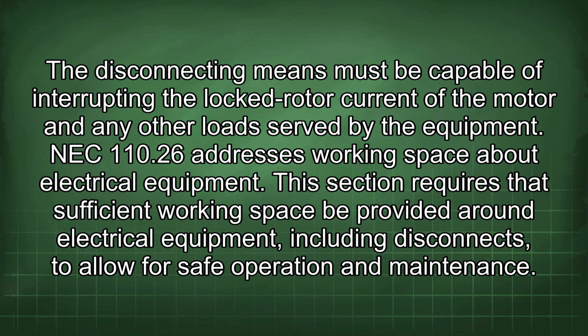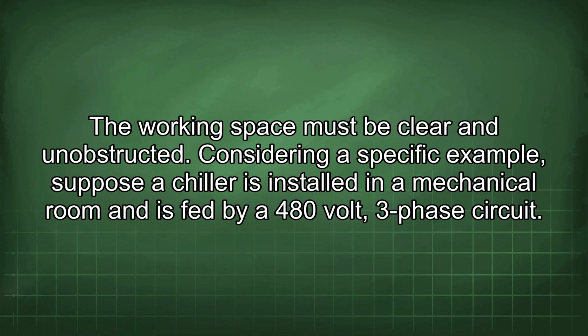NEC 110.26 addresses working space about electrical equipment. This section requires that sufficient working space be provided around electrical equipment, including disconnects, to allow for safe operation and maintenance. The working space must be clear and unobstructed.